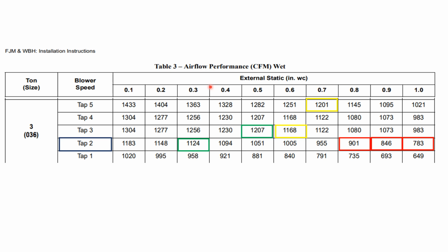To do that, you take the return and you add it to the supply static pressure. So you have a probe in your return, a probe in the supply. Anything over 0.3 is considered restriction, so we need to open that end up. Usually you're going to find the problem in the return. If you do it right, you'll see that your return is a lot higher resistance than the supply.